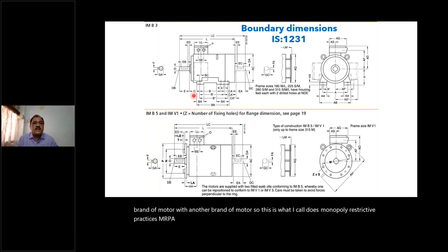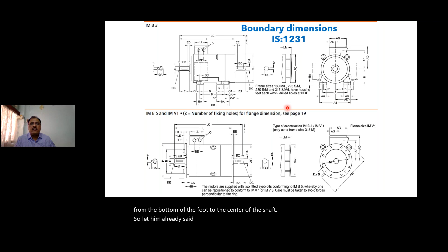D is the diameter of the shaft. E is the shaft length from the collar to the edge of the shaft. F and G are the keyway dimensions. Even this has to match. This cannot be different for different manufacturers. H is the center height. As you can see here, H is measured from the bottom of the foot to the center of the shaft. So like I've already said, A, B, C, D, E, F, G, H. These dimensions have to be identical for all manufacturers as per IS 1231.